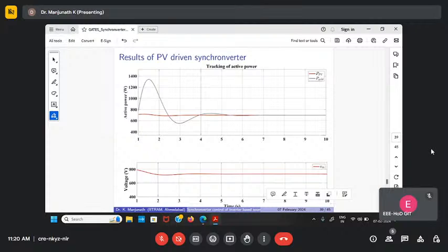The initial high transient is due to the initial high voltage of the DC link. DC link voltage should be maintained at 735, but initially it is close to 800. This might be the reason, and also the frequency as per the frequency control loop is higher. Because of these two reasons, the transient is huge in the beginning.